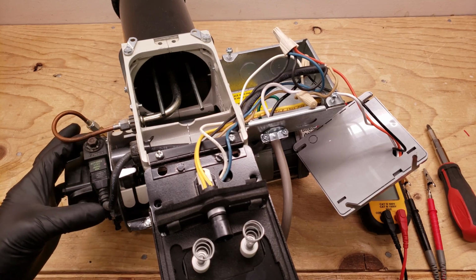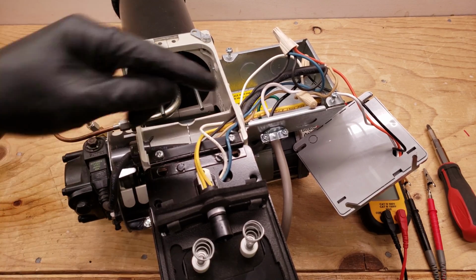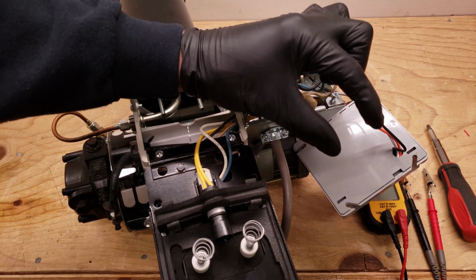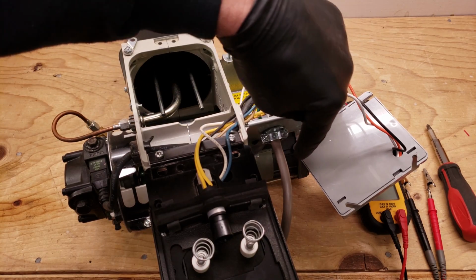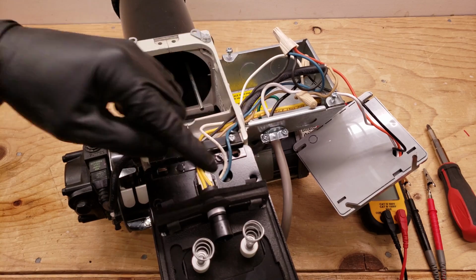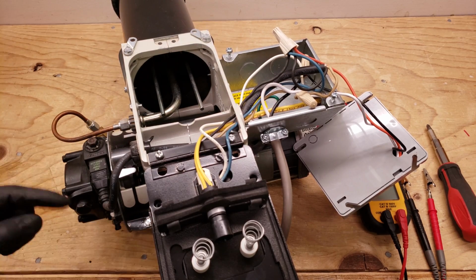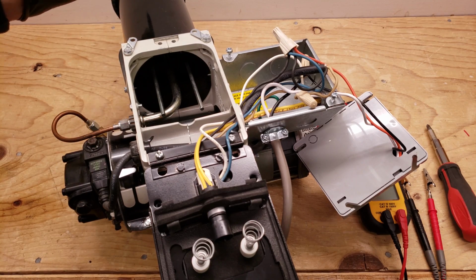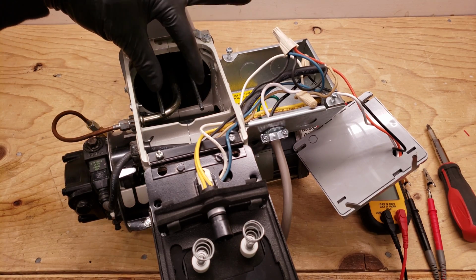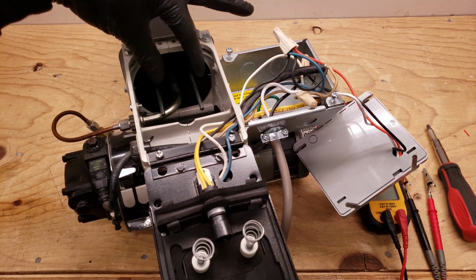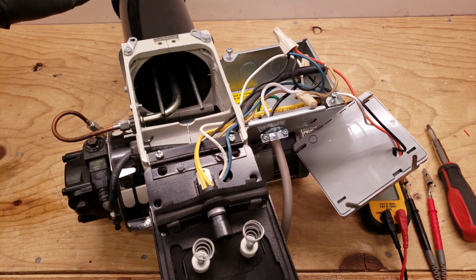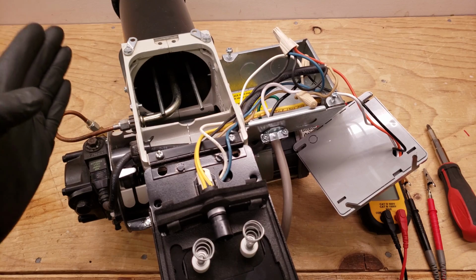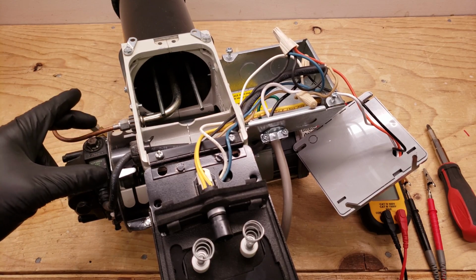Traditionally, on the older pump assemblies, you didn't have the solenoid. And what that meant was that on the primary control, when the connection between the T and T terminals opened up, then the primary control no longer sent voltage to the motor and to the transformer. But the motor is still free spinning, which means that the pump is still spinning and you're still pumping oil through the nozzle and into the heat exchanger. The issue is, since you're not powering the transformer, you're no longer sending the spark by the nozzle and you're not igniting that oil. So you're just spewing the oil into the heat exchanger area. So now that you have this solenoid, it's stopping the oil flow when you lose your 120 volts at the solenoid when the T and T terminals open up.